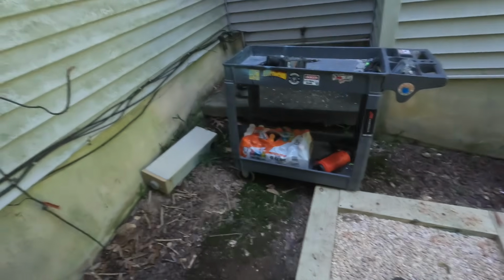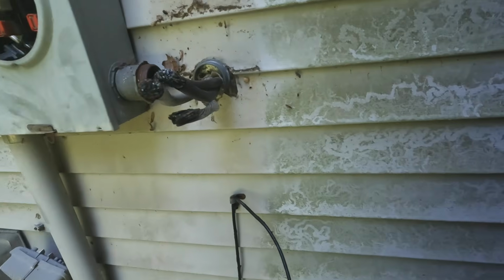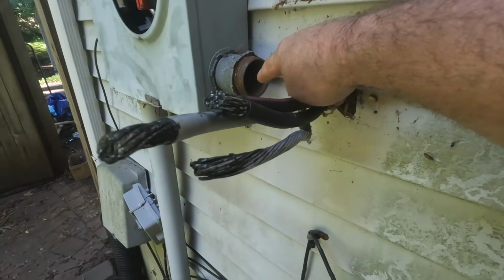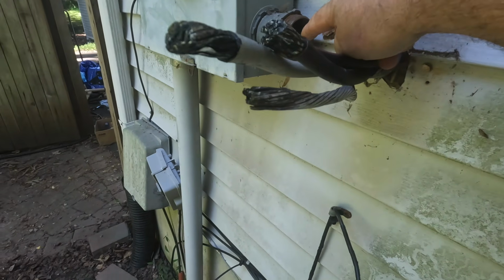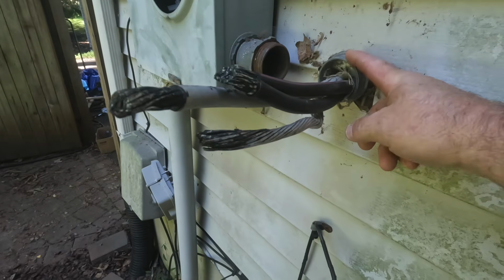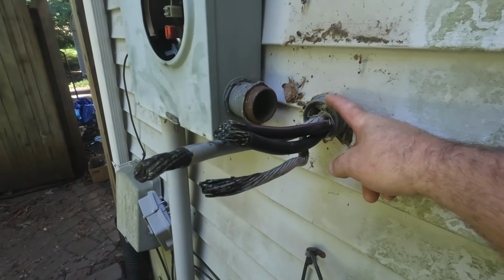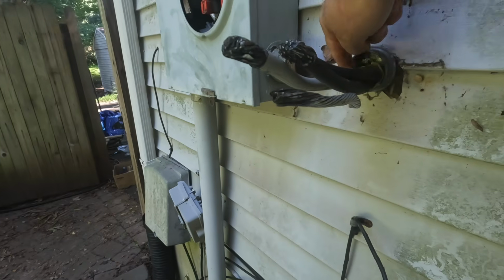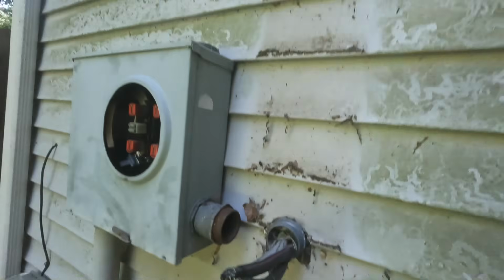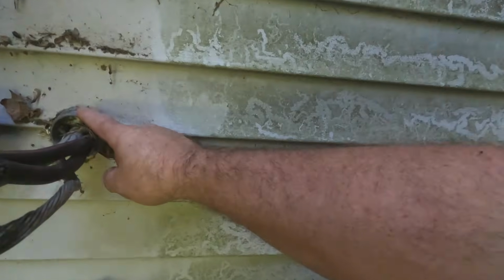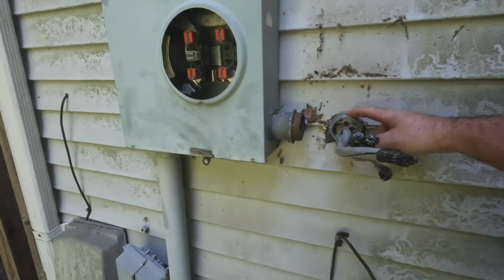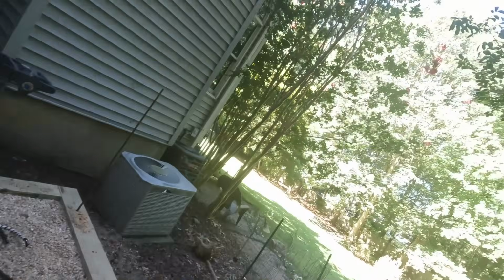All right, now this gets a little tricky here, right, because it's an existing installation. So I need to make sure that my knockout on the transfer switch is perfect right on here. Okay, so I'm just going to take a measurement, and then of course I make my measurement perfect right here as well, which is not going to be the simplest thing, but I'm going to do the best. Looks like the center of them are both lined up evenly there, so whatever my measurement is to the bottom of the knockout that I'm going to make in the transfer switch is going to be the same height as the one in the back. So that gives me a little bit of point of reference. Now let me get a tape measure here so I can get a good measurement. And some of this is going to be a little guesstimate because it's never perfect here. Never a perfect situation.